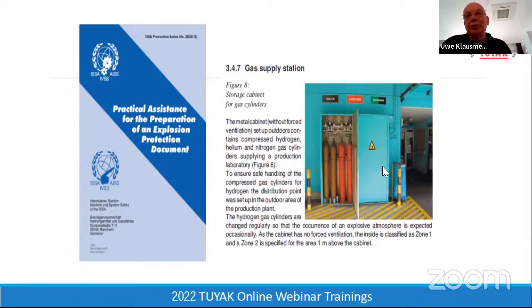As soon as you have a storage system, there's no need to design everything on your own - you just take an example from here and follow the description, and then you're happy. For instance, zone 2 is specified for the area 1 meter above the cabinet, so above the cabinet you must be aware that there's a 1 meter zone 2, not zone 1. Inside is zone 1, and that's it.